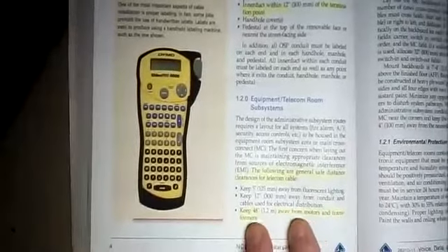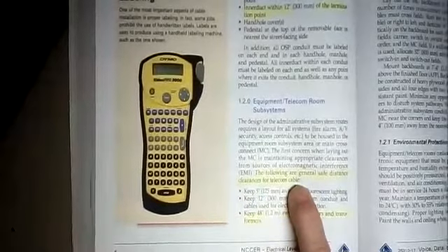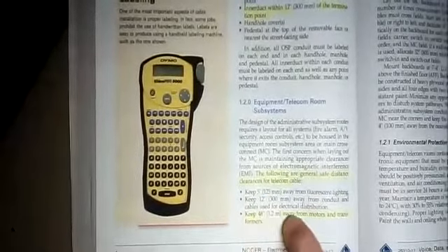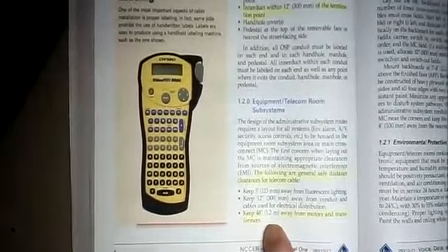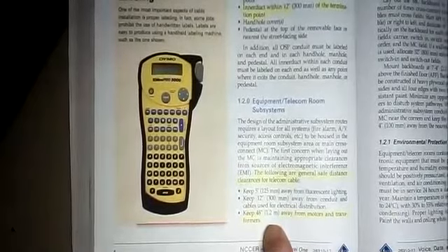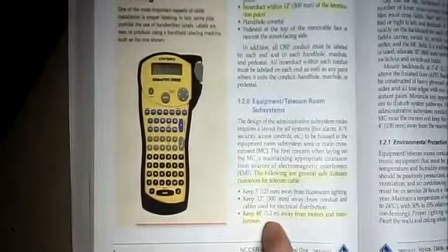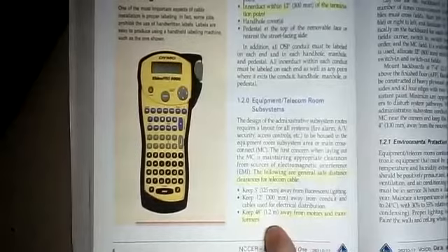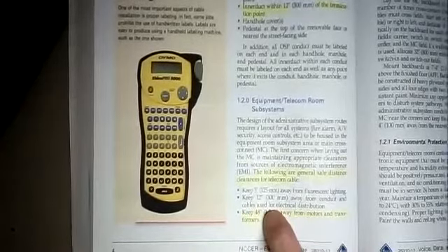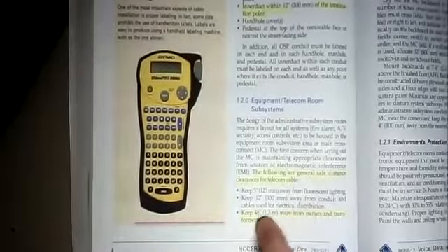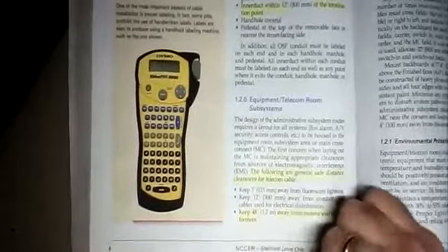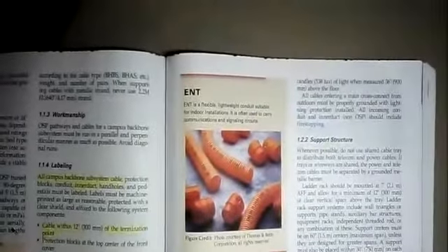The telecommunications room, the following are general safe distance clearances for the telecommunications room or telecom cable. You want to stay 48 inches away from motors and transformers. This is true with any cabling system, the riser cable, the horizontal backbone, any of the workstation cabling. You want to keep 48 inches away from motors and transformers. 12 inches away from conduit and cables used for electrical distribution. This is for your lighting system or for receptacles. Keep 5 inches away from fluorescent lighting. They cause interference. They can induce a small voltage and current in the communications cable. And that interference will scramble the message that you're trying to send over the cable.